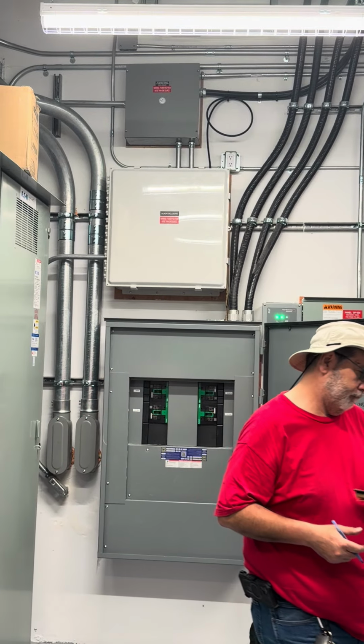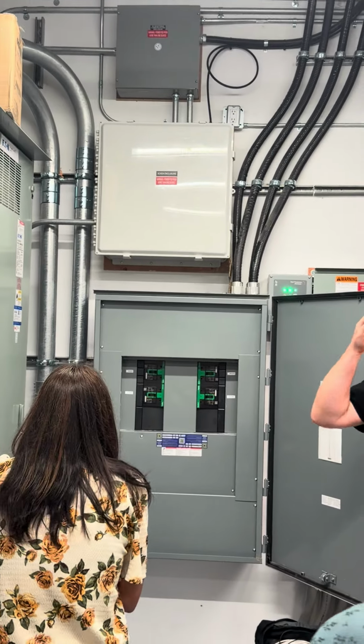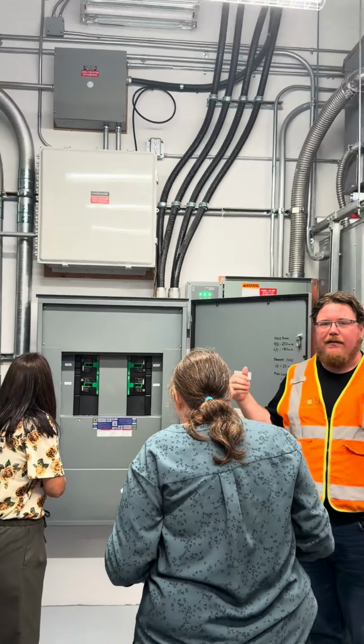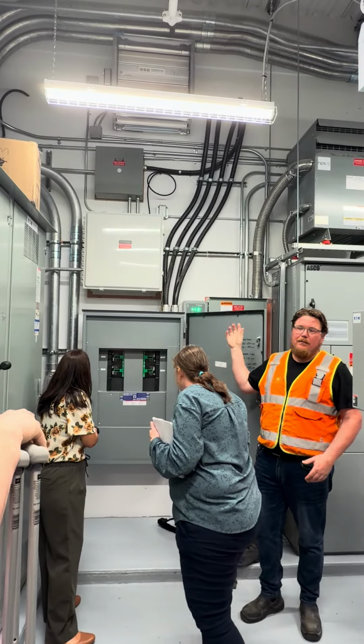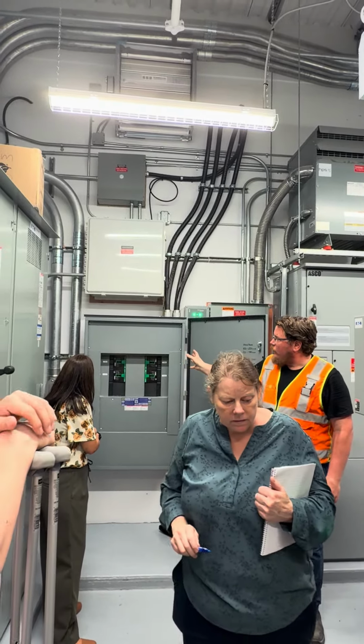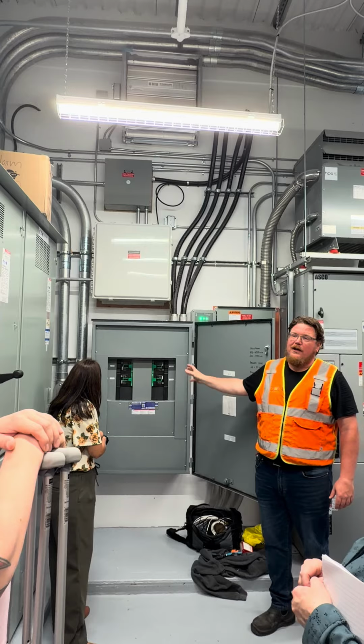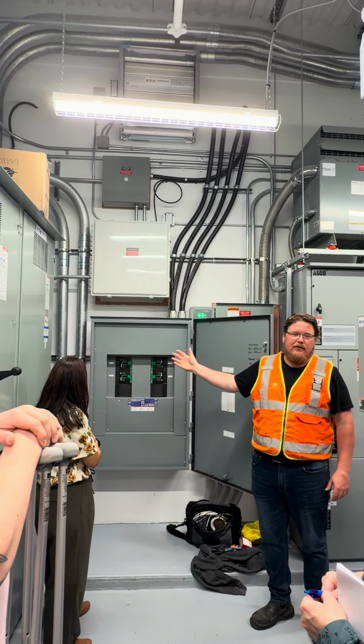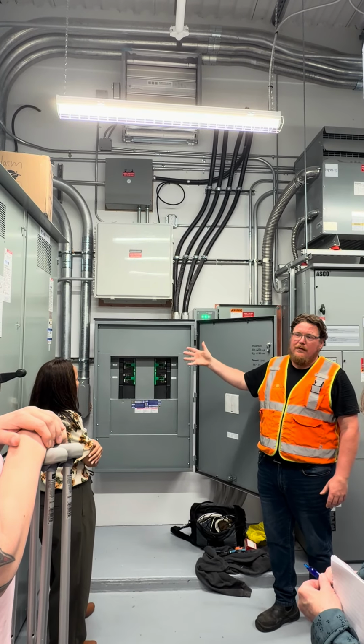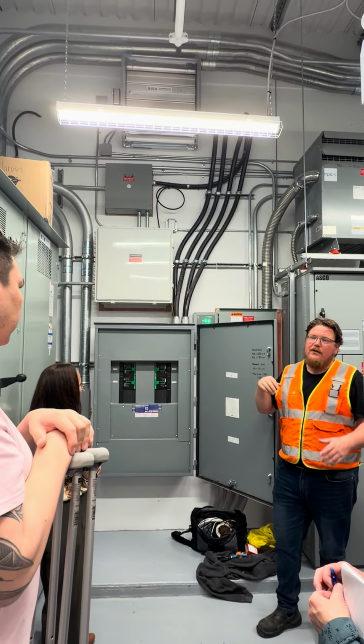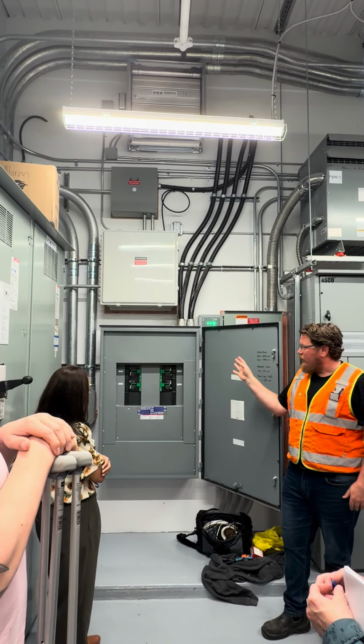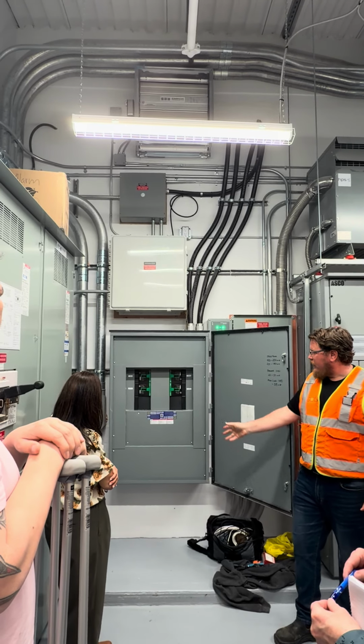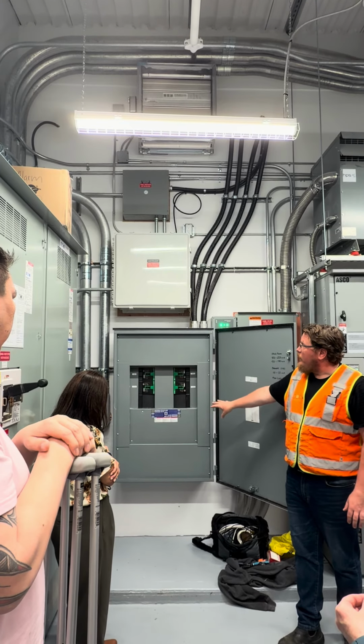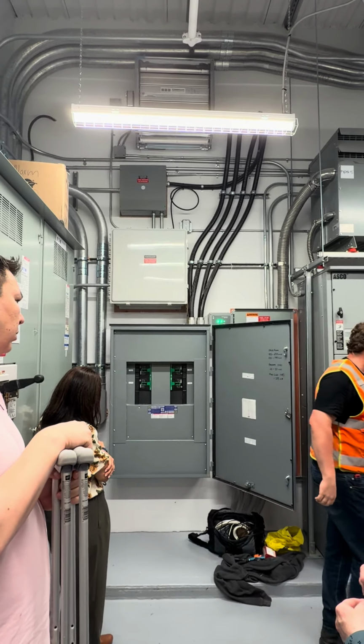So Tom had emailed me about infrared imaging and having a maintenance program related to that. This is one of the panels that would be part of that. Basically the system gets turned off, the covers come off, it gets re-energized, and then once it's warmed up, you do infrared imaging. So there is some coordination around what's happening in the area to accommodate that. But essentially this power flows from this panel directly outside.